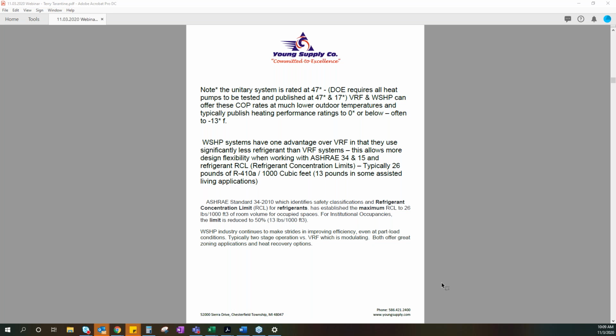One advantage a water source heat pump has over the VRF systems is in the amount of refrigerant that's included. In VRF systems, we're using refrigerant to transfer heat around the system. In water source heat pumps, of course, we're using water. So the more refrigerant you have, we start to run into some code issues, and that's ASHRAE 34 and 15, where we're talking about refrigerant concentration limits. For most applications, we're allowed 26 pounds of 410A, the primary refrigerant we're using today, per 1,000 cubic feet. And for some institutional, like assisted living, memory care, different things like that, we cut that in half to 13. So it is something that we'll talk about a little bit more at the end, but we need to be aware of that in our design phase. And we just talked a little bit about the ASHRAE.